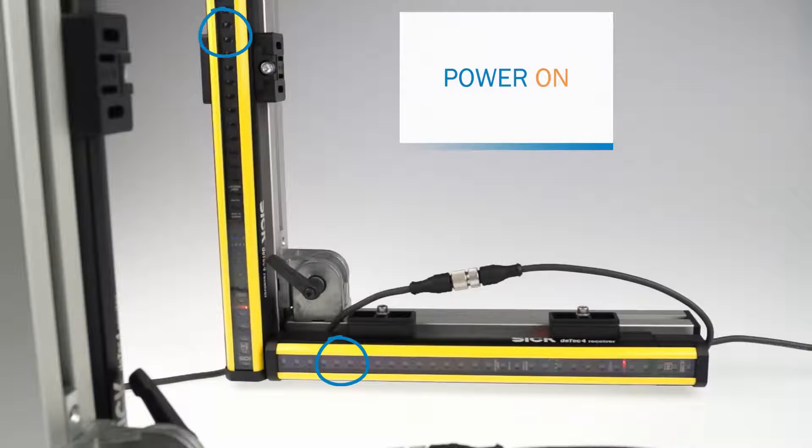Now, the field LEDs of the devices are flashing green. This is the sign that the devices have entered the configuration mode and the cascading has been successful. Additionally, the blue alignment LED 2 is flashing to show that the host-guest cascade is configured.